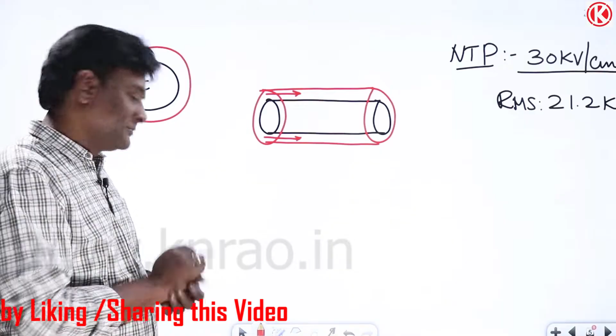Around the conductor, electric field intensity will be maximum on the surface of the electrical conductor - I already know this. So on the surface, if the voltage gradient is more than 30 kV per centimeter maximum, what will happen? The air around the conductor will become an electrical conductor and will participate in the electrical current.